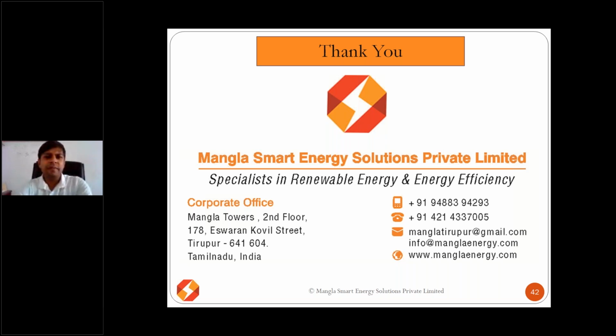Yes sir, I'm getting your question. The reply has two possibilities. Possibility one is to go for a hybrid system wherein on-grid you can have battery storage. Those systems are available, so you can go for that. But it is not possible for bigger capacity plants because you cannot have that many battery capacities for bigger size plants. If it is small or medium sized plants, up to 10 or 15 kilowatt, it is possible. There are also installations in Delhi government buildings with 100 kilowatt using hybrid systems, where the battery UPS will be supporting and on-grid will be functional even if battery power is coming to the inverter, and it will be working.